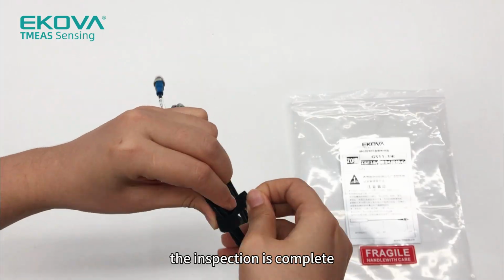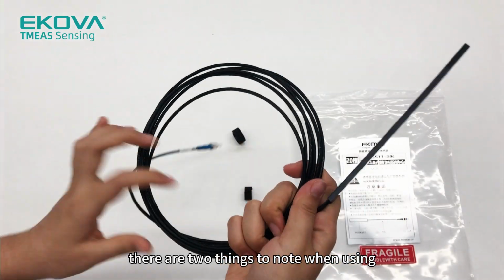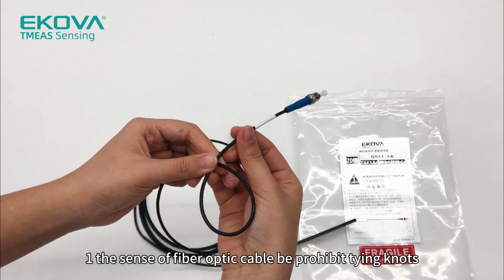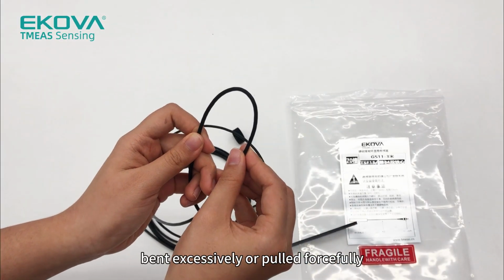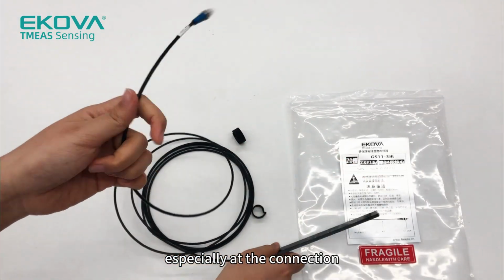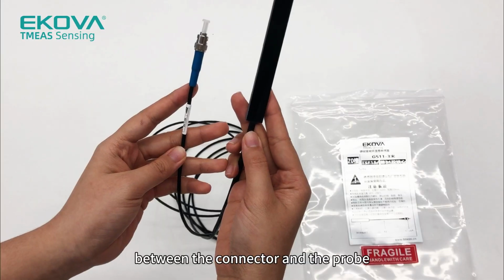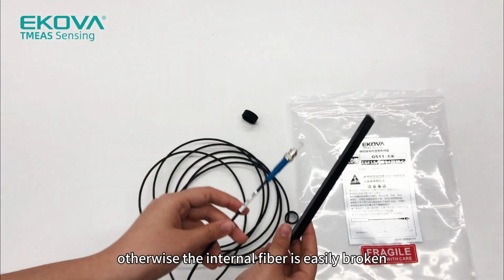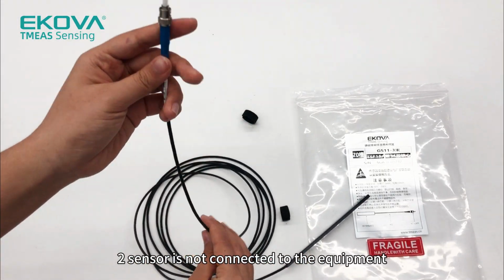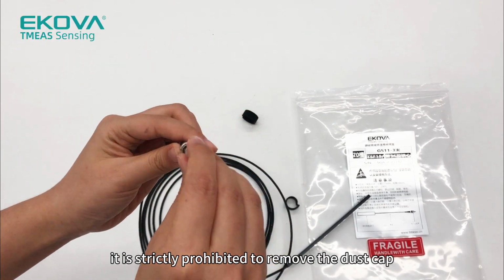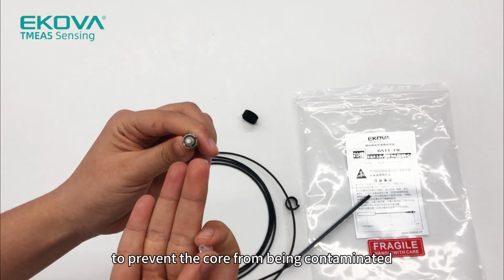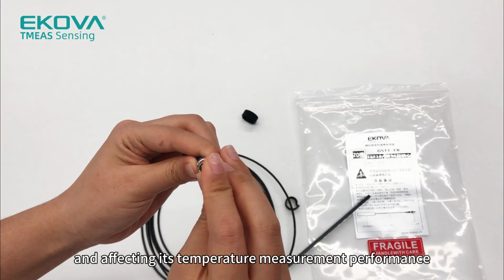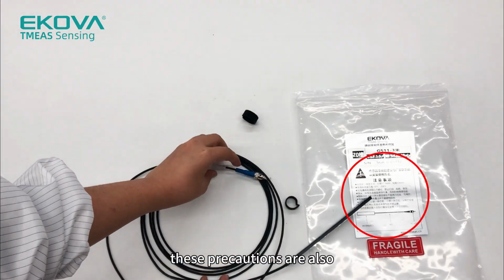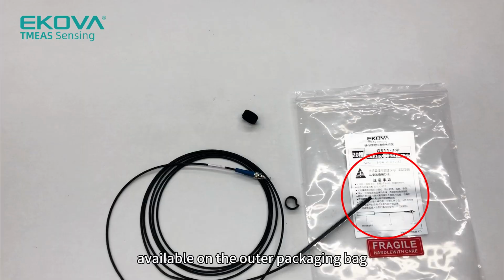The inspection is complete. There are 2 things to note when using. 1. The sensor fiber optic cable is prohibited from being tied in knots, bent excessively, or pulled forcefully, especially at the connection between the connector and the probe, otherwise the internal fiber is easily broken. 2. When the sensor is not connected to the equipment, it is strictly prohibited to remove the dust cap, to prevent the core from being contaminated and affecting its temperature measurement performance. These precautions are also printed on the outer packaging bag.